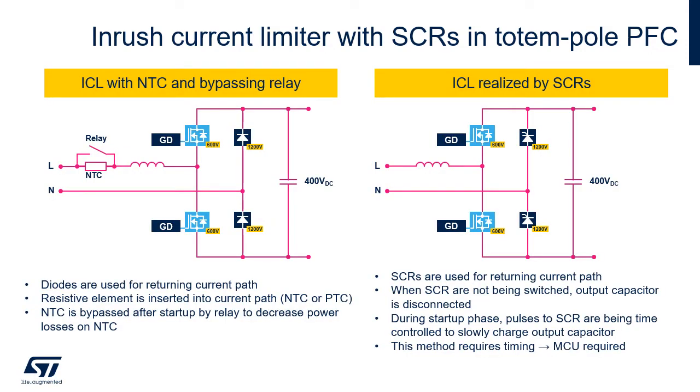When inrush current limitation is realized by a relay, standard diodes are used as a return current path, and the current at startup is limited by a resistor in series, which is short-circuited by the relay after a given time. In a solution with SCRs, at startup the SCRs are enabled just during proper pulses, thus allowing a slow charge of the output capacitor. This can be done just by a microcontroller.